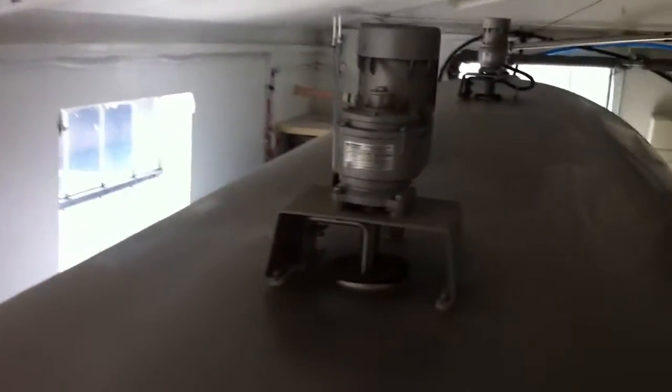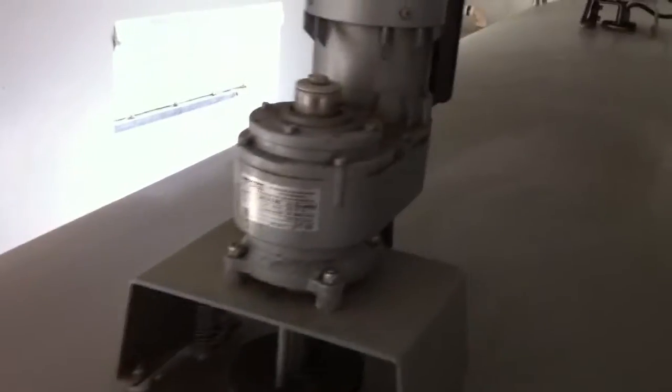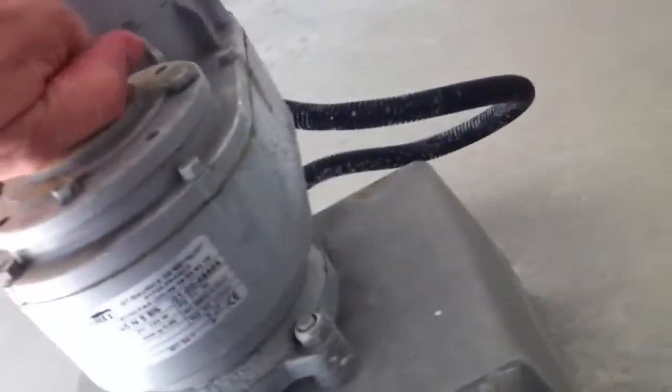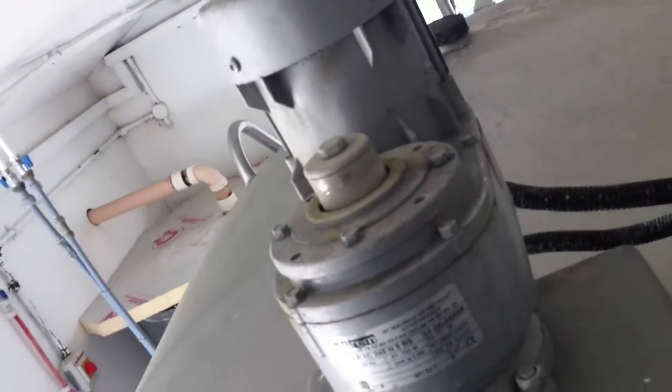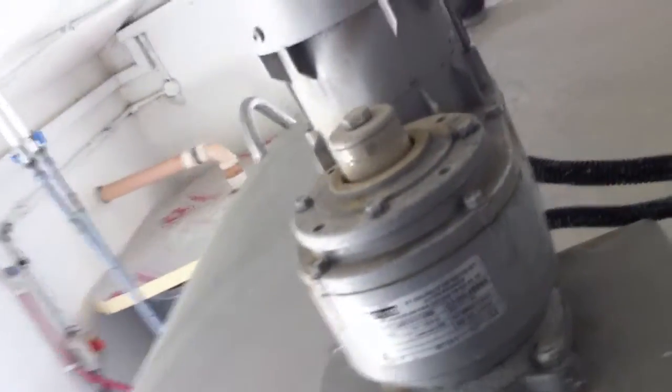Let's put that on the stir. The front agitator is running, but the back one isn't. It's probably got a bad capacitor in there. I'll check them both.